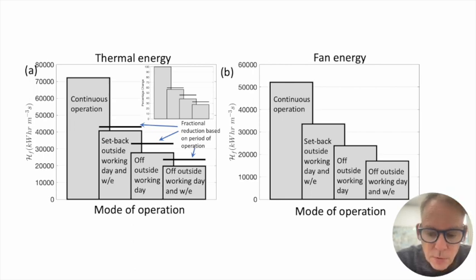If it's turned off outside the working day, which might extend to Saturday and Sunday, then there's a 60% reduction, and if we switch off at the weekends, then there's a 70% reduction. Coupled with this, the removal of the anaesthetic room will also lead to a reduction of about 15%. So all in all, we can have an 80% reduction if we design our spaces to take into account new ventilation strategies and design them so that they can be turned off through a safe and secure process that doesn't affect surgical site infections.